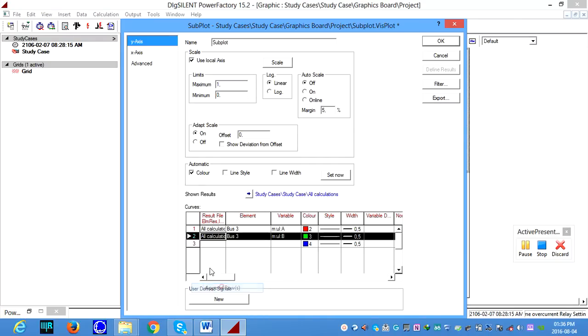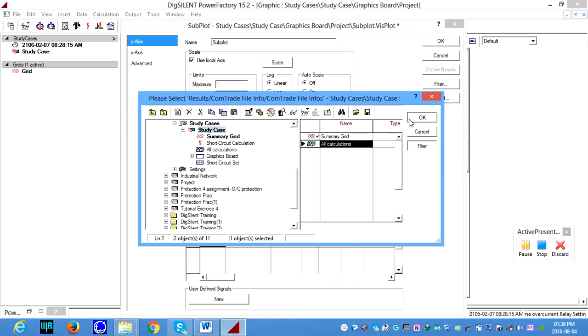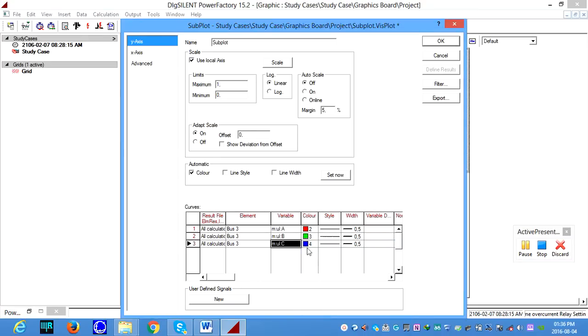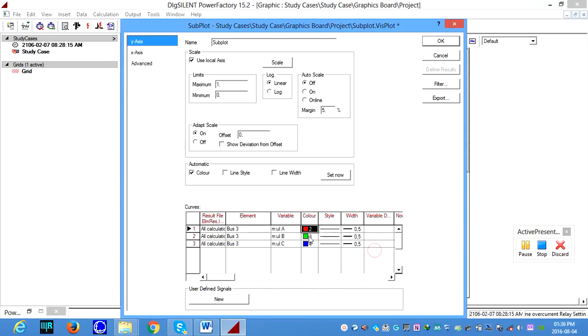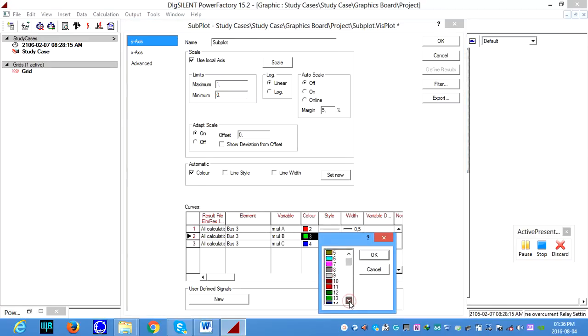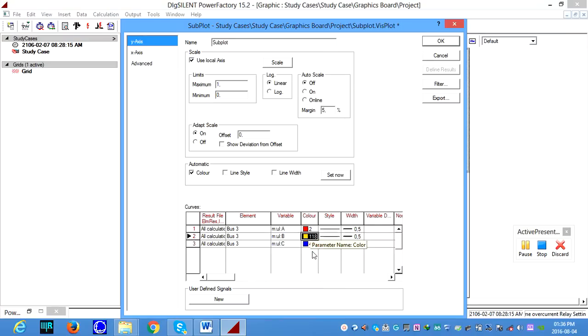And again append the rows, go for all calculations and select the element bus 3 and select the variable that is supposed to be phase C voltage magnitude. The colors are also there, but if you want you can change the colors, but by default I leave it. Otherwise if you want RYB, it looks like the same thing, R red for A phase. If you want you can change to yellow for Y phase and blue for B phase in terms of RYB. But this is optional.